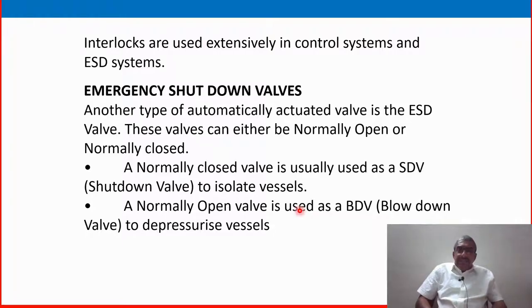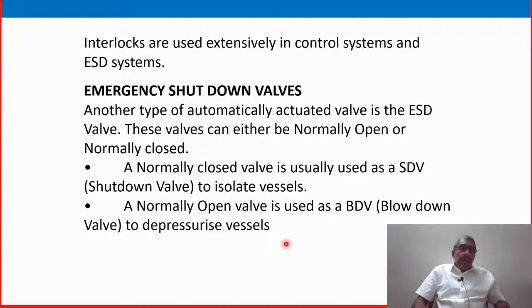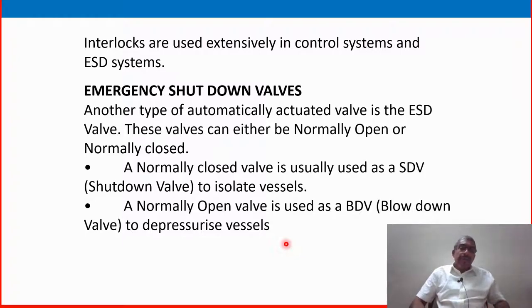Interlocks are used extensively in control systems and ESD systems. Another type of automatically actuated valve is the ESD valve. These valves can either be normally open or normally closed. A normally closed valve is used as a shutdown valve to isolate the vessel. A normally open valve is used as a BDV — blowdown valve — to depressurize the vessel. A video exclusively on emergency shutdown valves has already been released; please watch it for full detail.